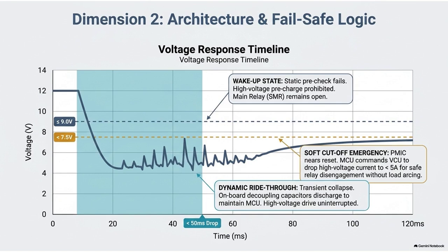If the voltage drops just enough that the magnetic grip is weak, but not enough to let the springs snap the contactor completely open, the vibration of the moving vehicle takes over. The copper contacts begin to bounce. They separate by a fraction of a millimeter, then smash back together at incredibly high frequency. And when you separate two pieces of copper carrying 300 amps of 400-volt direct current by a fraction of a millimeter, the electricity does not just politely stop flowing. You ionize the tiny air gap between the pads. You create plasma. You basically create a localized lightning storm inside the contactor housing.